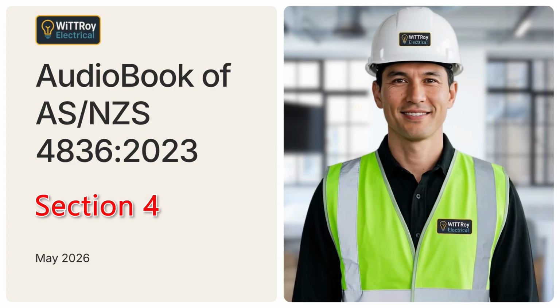Clause 4.3.3 Hazardous areas. Clause 4.3.3 explains work in hazardous areas. A hazardous area is a place where flammable gas, vapor, or combustible dust may be present. Examples may include petrochemical installations, grain storage areas, and flour mills. Work on or near electrical installations or equipment in hazardous areas must only be performed using safe work methods suitable for that site. Normal work methods may not be safe in a hazardous area. A spark, hot surface, static discharge, unsuitable tool, or unsuitable electrical equipment may cause ignition. Workers may also need specific competency for hazardous area work, depending on the regulatory requirements and the type of work being carried out. In simple terms, hazardous areas require special control.